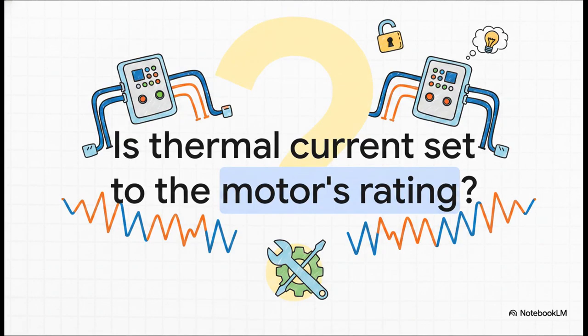I want to leave you with a question to chew on today. If your drive is protecting a motor right now, out in the field, do you know for sure if the thermal current is set to the motor's actual rating, or is it just sitting at the drive's default? Check your panels today. Talk to your technicians, because assuming your drive is protecting your motor without actually verifying that ITH parameter, well, that's a massive gamble you really don't want to take with your equipment.